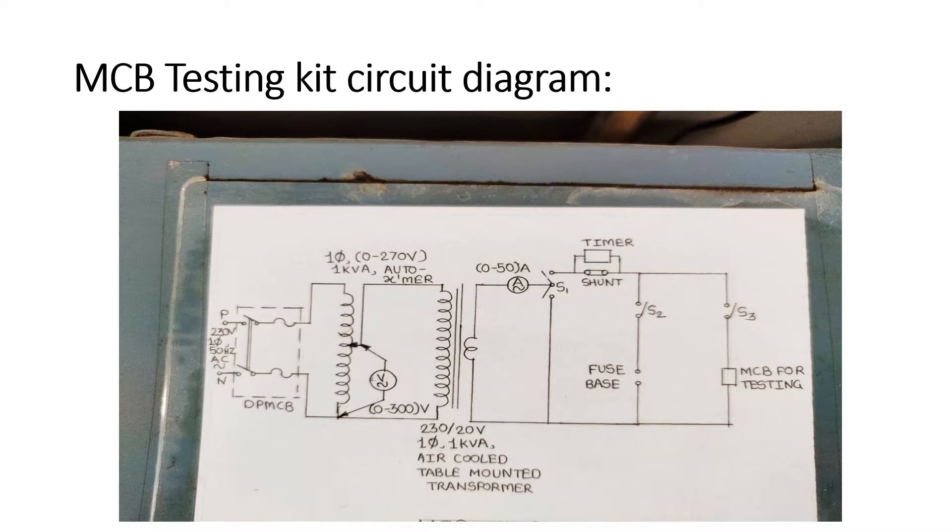So this is the basic circuit diagram of our MCB testing kit. In this particular diagram you will find that we are going to perform MCB test. We want to test the MCB with the help of load test. But as in our lab we are not having higher rating load or load bank, so instead of that what we are doing here we are conducting just like a short circuit test.